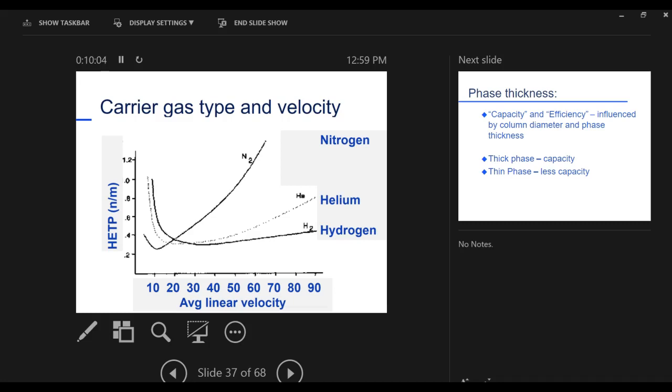That's good. But this is the linear velocity, how fast that carrier gas is moving, how fast my separation goes, how much analysis time I have. If I have a really slow gas rate, it's taking me forever to get this done. If I decide I really want to get my analysis done more quickly, I'm going to speed up the gas flow. I'm going to get a separation, but if I choose to do that, this is taking me forever, wonderful separation. I can't afford to wait for long. I jack it up with something like this. Now I'm not getting good separation. So nitrogen, ideally, is the best separating gas. But I can't afford the time. It costs me too much in time.